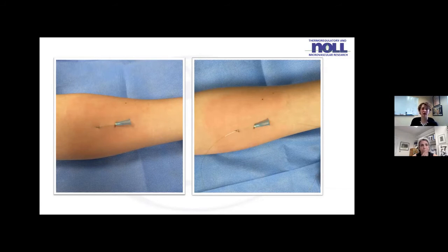and then test the probe utilizing an inert solution, so either Ringer solution or saline solution. And what you look for is to see small bubbles of fluid perfusing or coming up out of that membrane that you can see here portrayed as that white portion. And then you'll also see a bubble of fluid come out the end of that microdialysis probe.